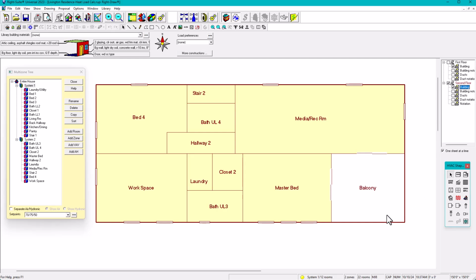The sun path is more on the south. So technically on the south, we're going to have more cooling load than on the north side. So in this scenario, I'm gonna make these 4 rooms a different zone than these other 4 rooms. These rooms are gonna be on the north side and these rooms are gonna be on the south side. That's gonna be a good example.